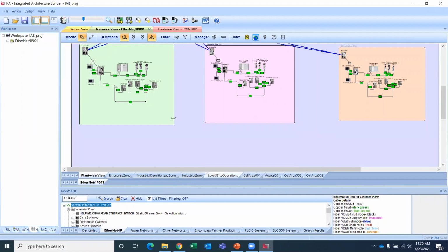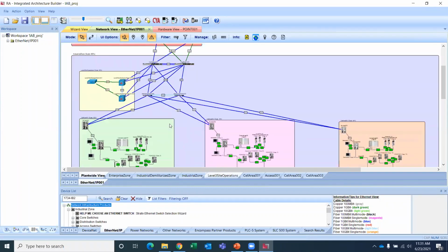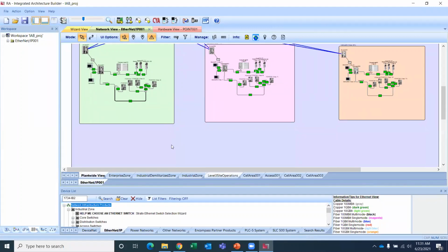Okay. So now let's say in industrial manufacturing, automation, networking, if you work at an end user facility and you get a new machine or you get a new line installed, unless you specify during the commissioning process with the OEM or with the system integrator who's going to be coming in and installing that and helping getting it up and running, like what IP address scheme you're going to use, you may end up with a local area network of a machine that's something generic, like a 192.168/24 network. But what happens when you try and take that piece of machinery and you try to apply it to your architecture as a whole, your enterprise architecture as a whole? Well, unfortunately, you might run into issues with duplicate IP addresses. It might cause routing issues because there might already be a route for that 192.168 existing within your network.